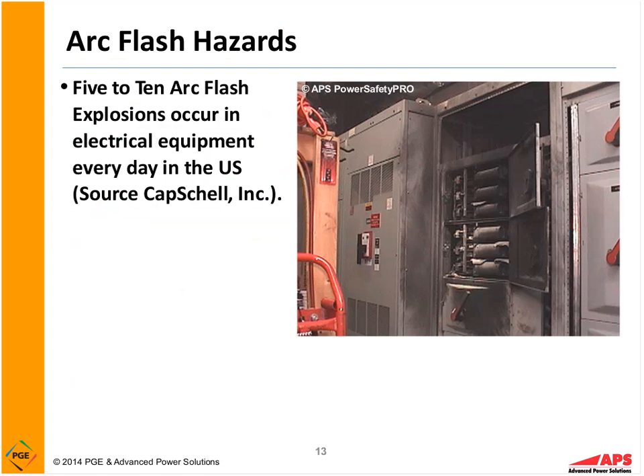Okay, so 5 to 10 arc flash explosions occur in electrical equipment every day in the U.S. 5 to 10. Wow, that's a lot. So this picture here in this slide is from a friend of mine in Ohio. He opened up this 600 amp fusible disconnect here, and when he opened up the disconnect, he was wearing all natural fiber clothing. The arc occurred on the primary side.